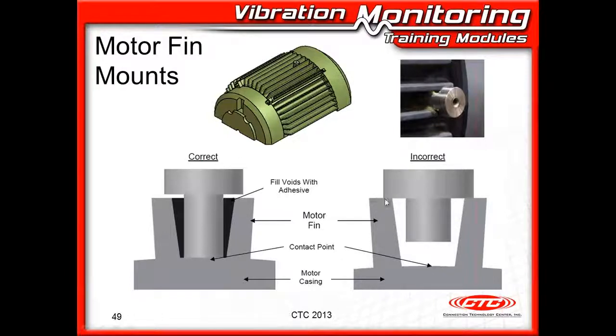This is incorrect. You do not want the fin mount probe resting on top of the cooling fins. The idea here is to get the fin mount probe to rest on the casing of the motor. So you're trying to get that bearing to transmit the vibration up through the casing and not get involved with these fins, which have some of their own frequency components to them due to their construction. So try to get the fin mount probe put into the casing of the machine, then fill the sidewalls with epoxy, having this air gap here above the fins.